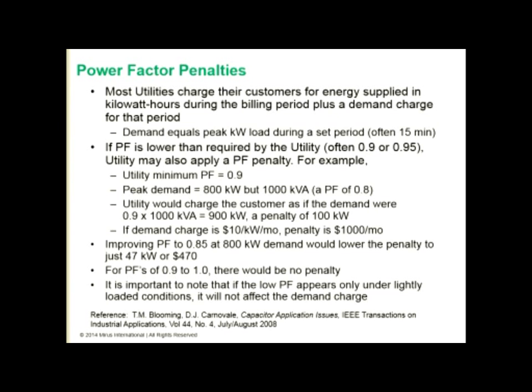And it is important to note that if the low power factor appears only under lightly loaded conditions, it will not affect the demand charge. This is because demand, by definition, is only at the heavy loading conditions. So we do not need to have particularly high power factors at lighter loads.